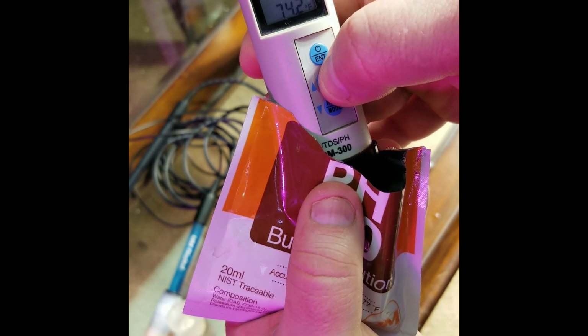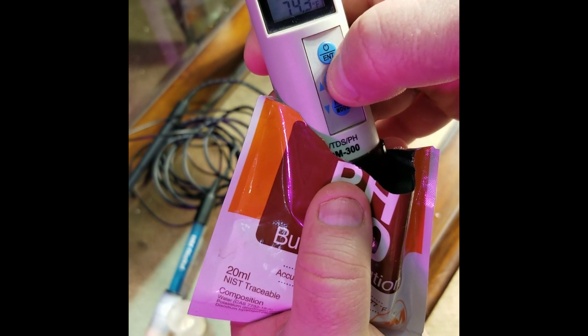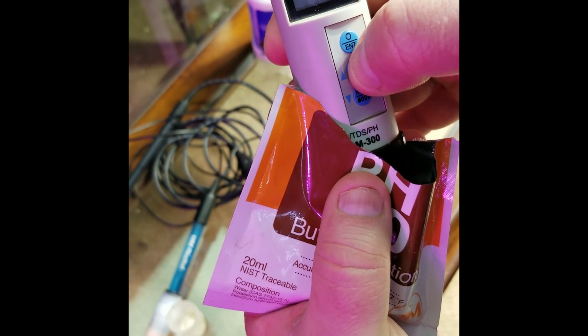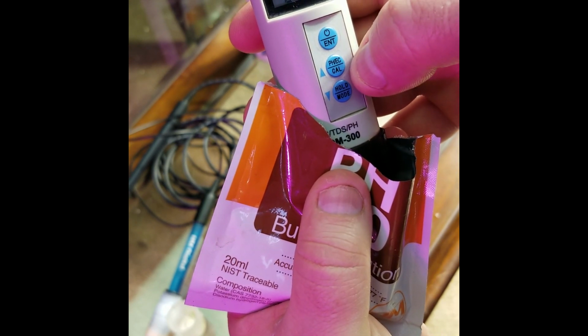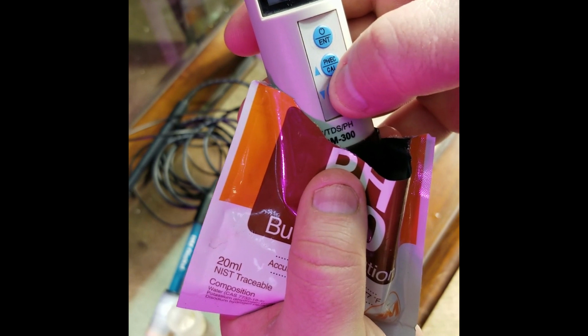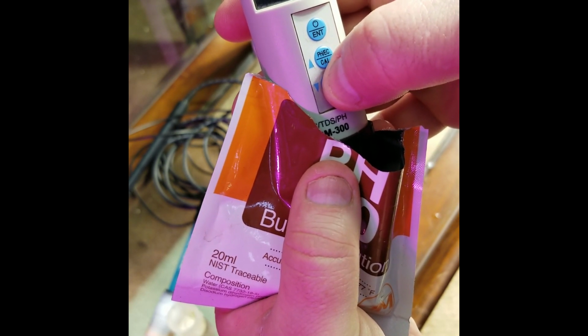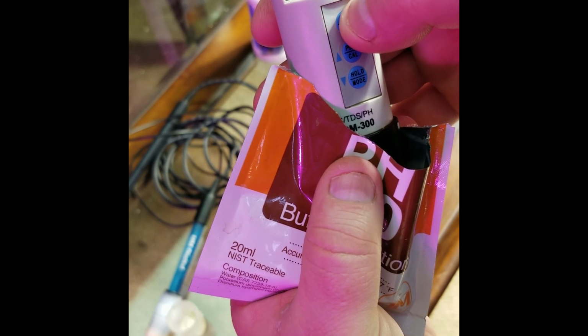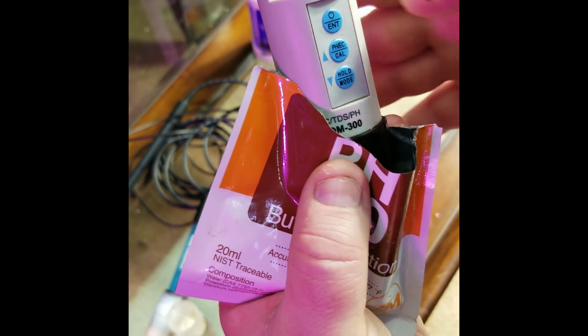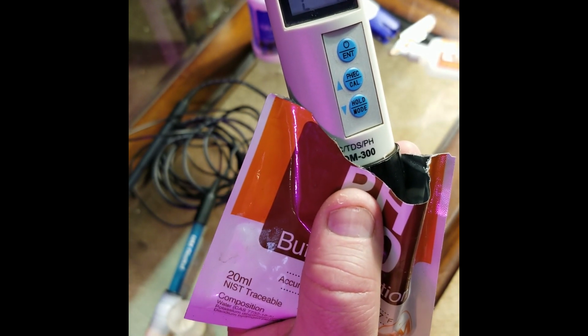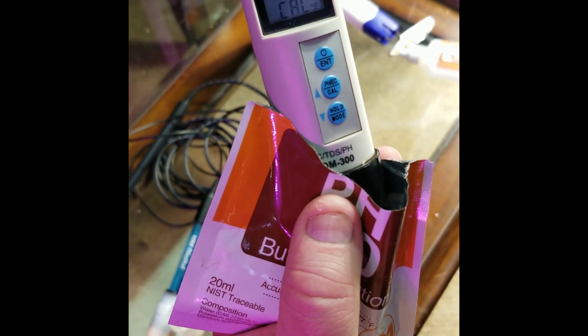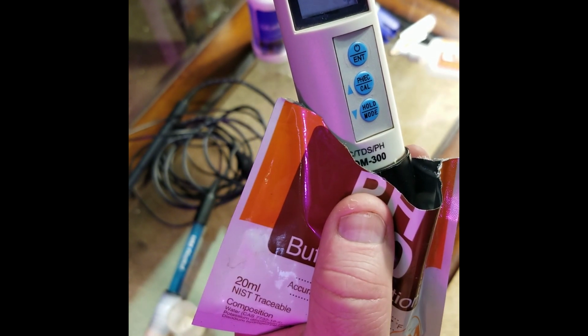So we're going to hold for calibration. It's going to sit here and flash. It's at 7.1. Now we're going to hit the down arrow button to tell it that it's 7.0, and then we hit our enter. And then it sits there and waits to make sure it doesn't drop or raise. And then it should say end, and it should say 7.